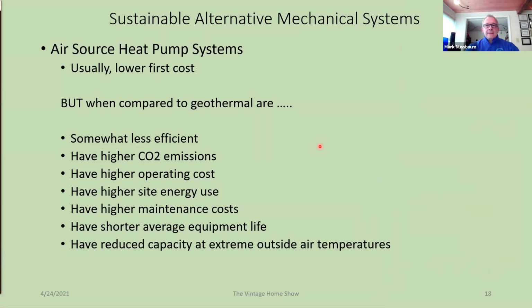Air source heat pumps. The big thing with the air source heat pump is it's almost always going to be lower first cost. The geo will pay for itself over time, but it might take a while. But when you compare it to geothermal, it's less efficient, with higher CO2 emissions, operating costs, site energy use, and maintenance costs. Again, I've got a box sitting outside and a box inside, so inherently I just have two machines to repair or keep running rather than one. Shorter average equipment life, and that's again because the exterior unit is going to age faster.